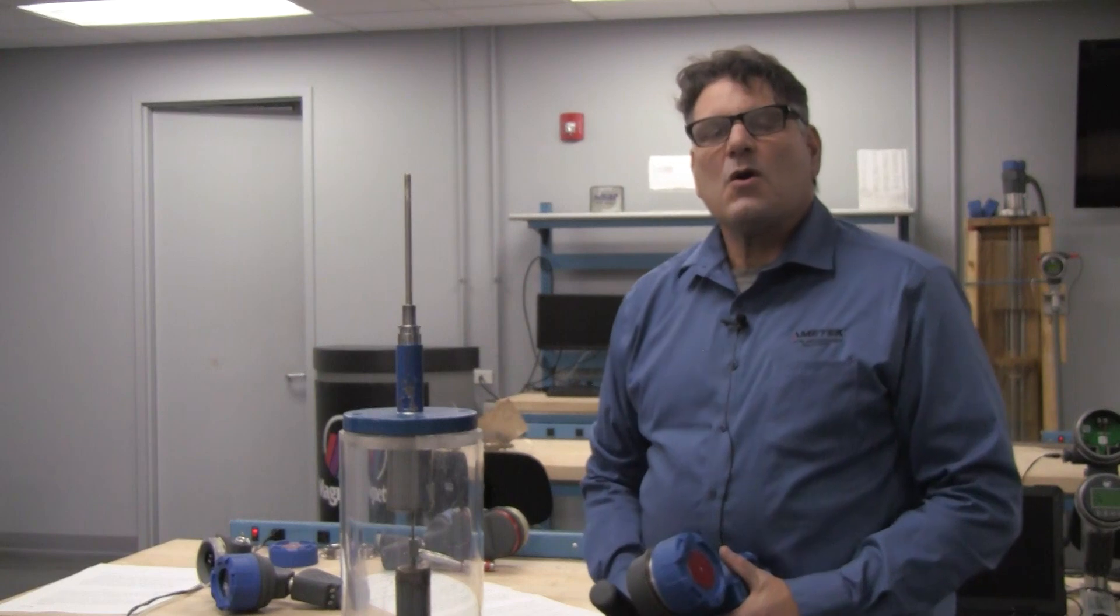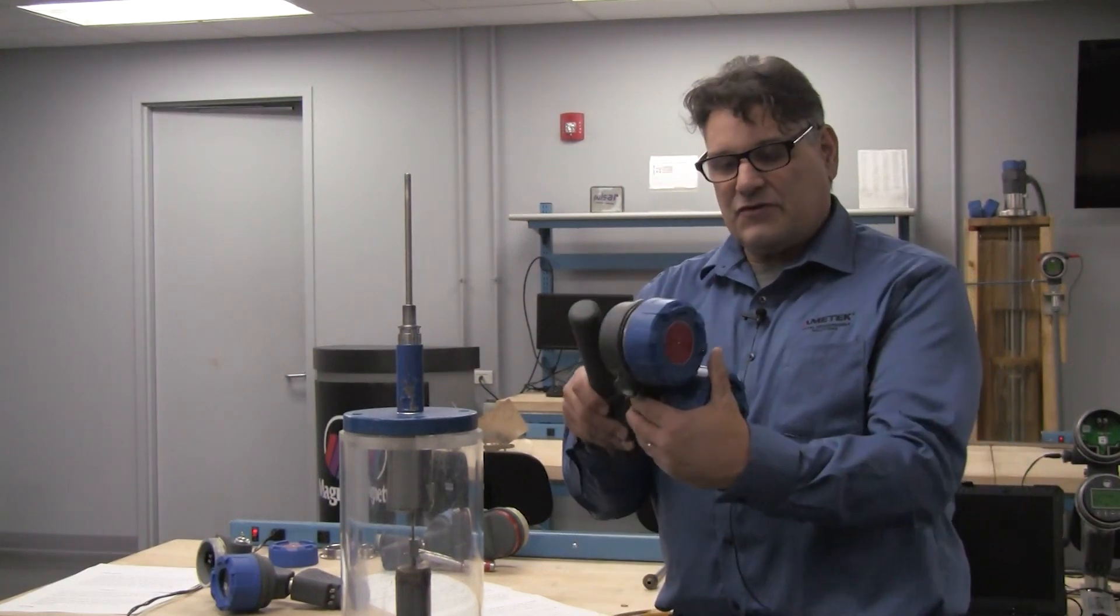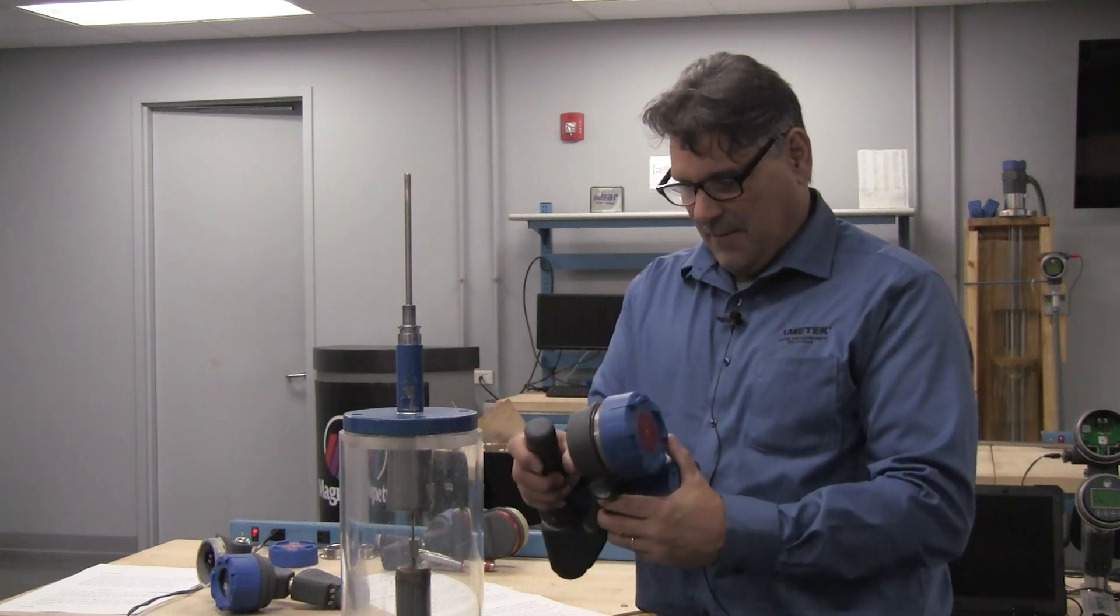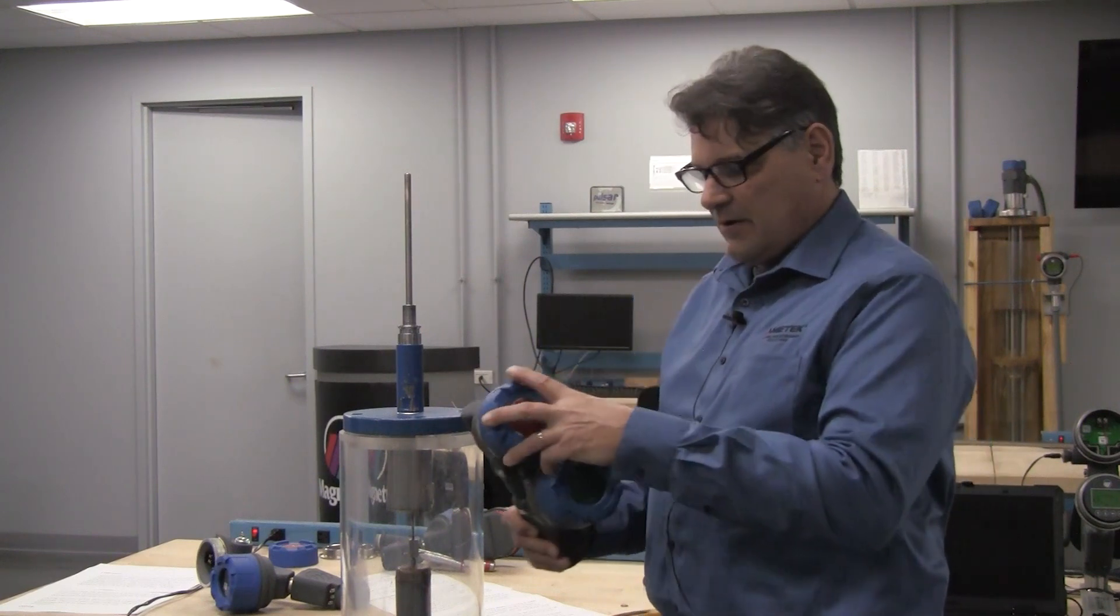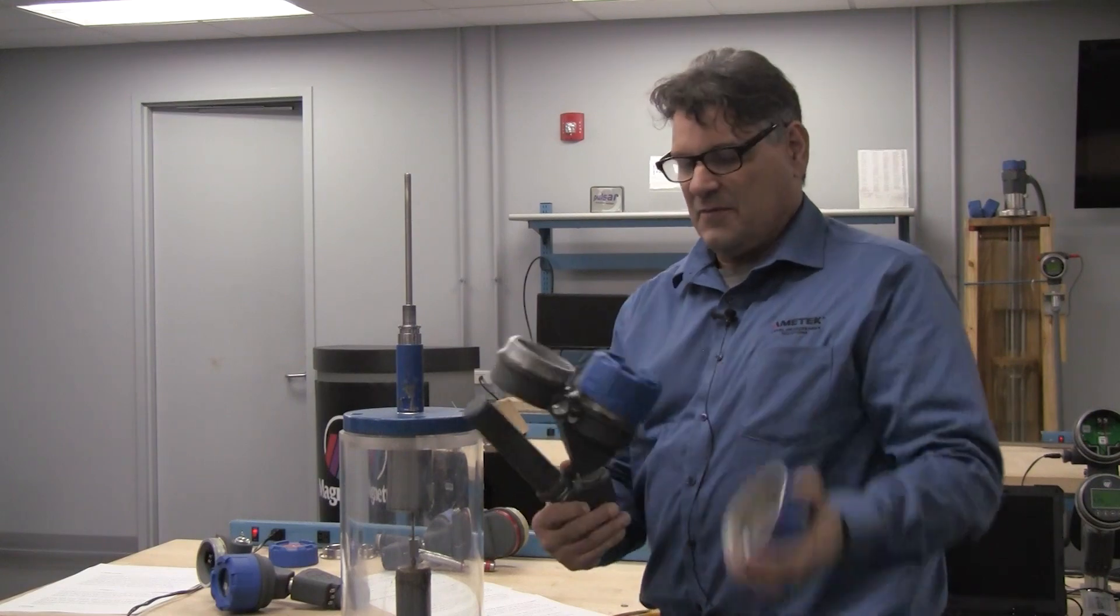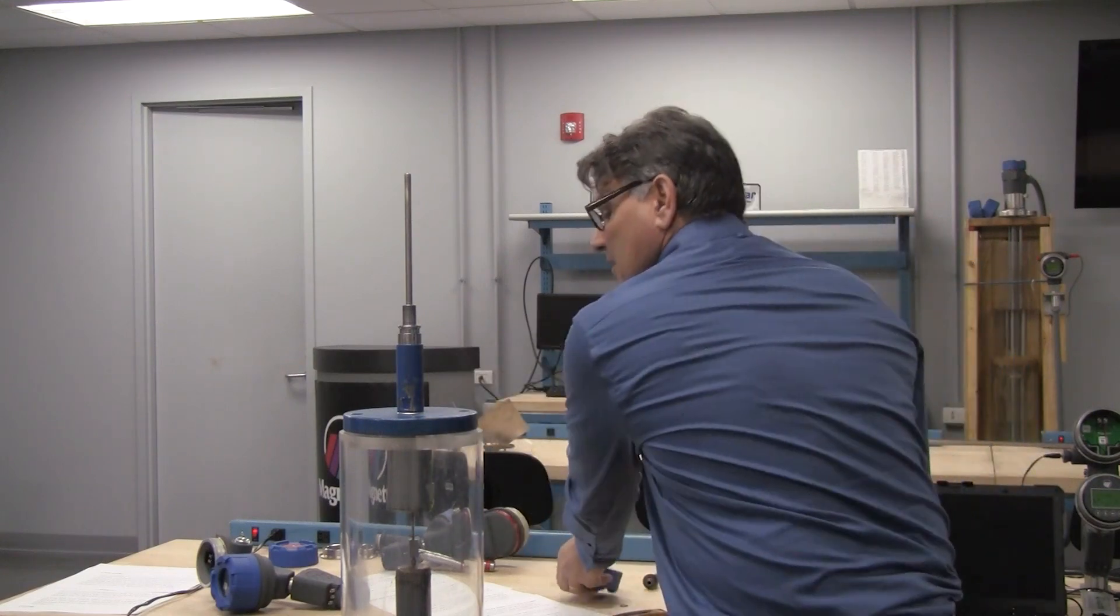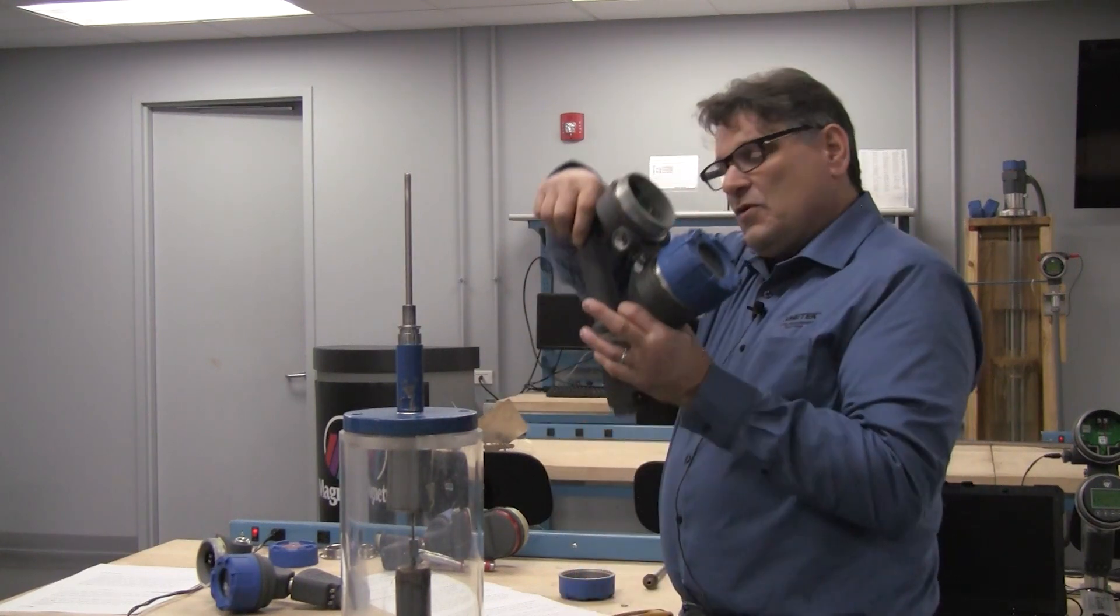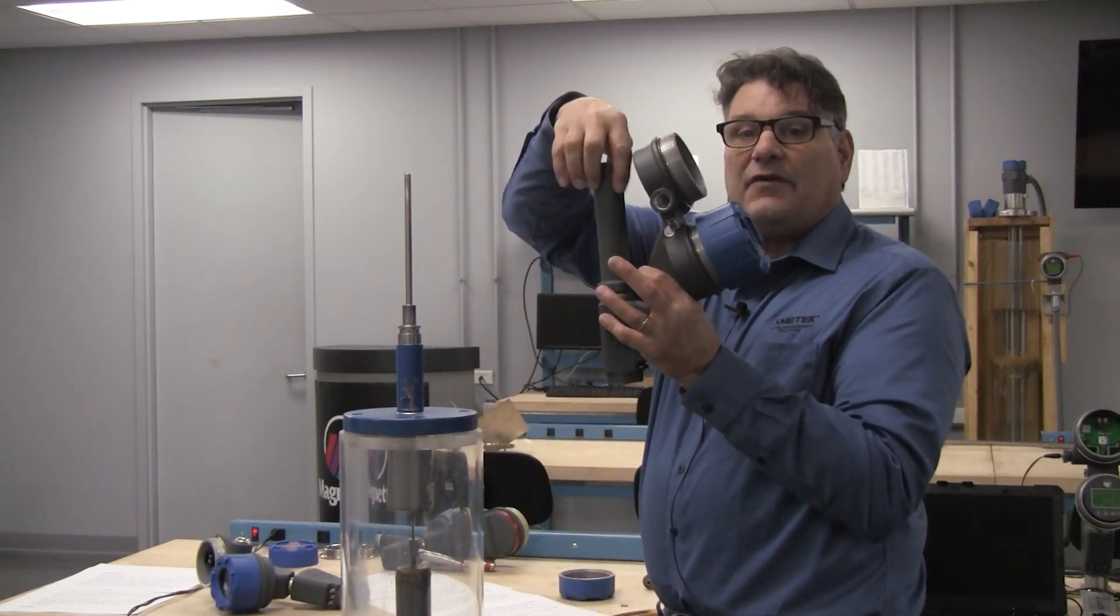Now that we've removed the old level transmitter, we're going to get the new transmitter and get it ready to install on the existing equipment. To start, you could remove the wiring cover from the top so when you get it on, you'll be able to wire that up. And then, you're going to remove the LCD cover.